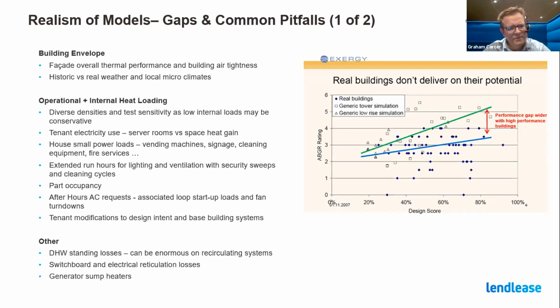Before we go to mechanical, we found in Australia that the standing losses from domestic hot water systems can be circa 250% of the useful heat that's actually delivered out of the tap. Yet we're still doing recirculating systems. It's just an enormous energy drag, and at least accounting for it, if not trying to improve on it, is really important.